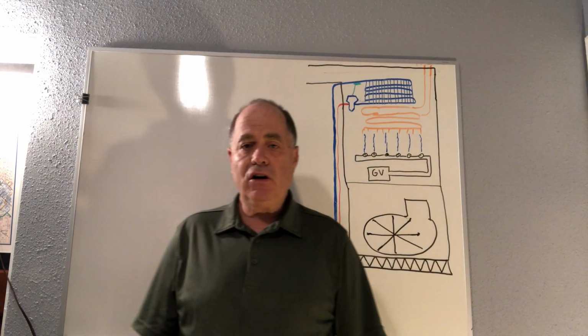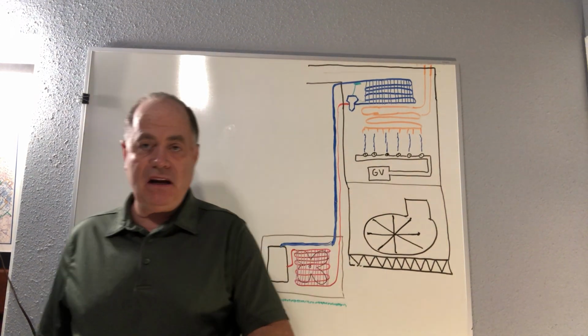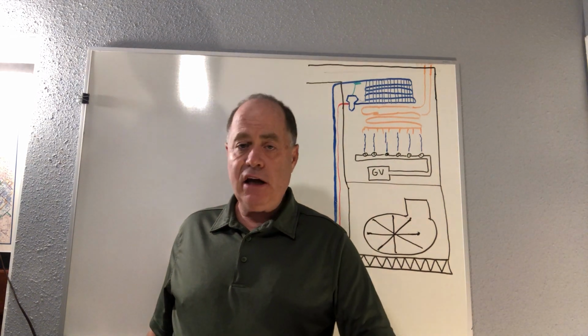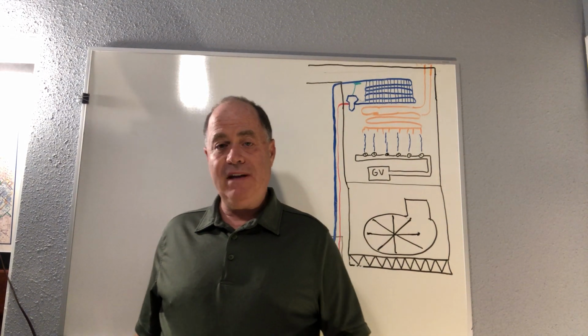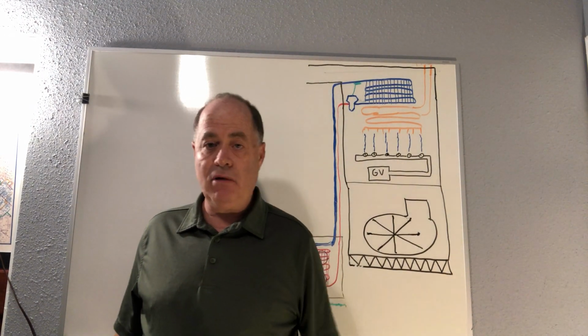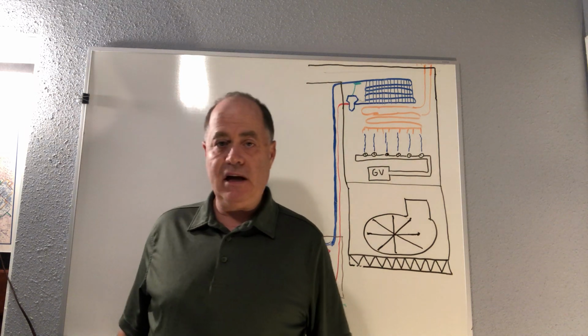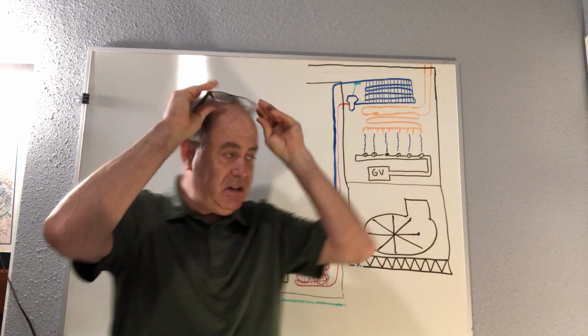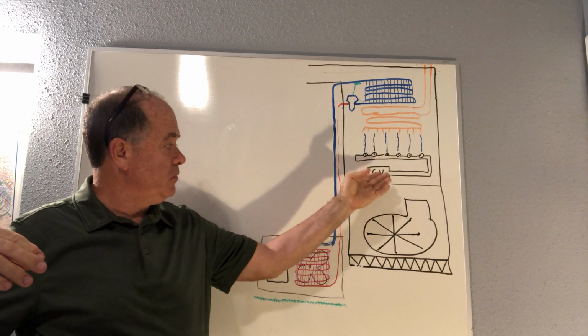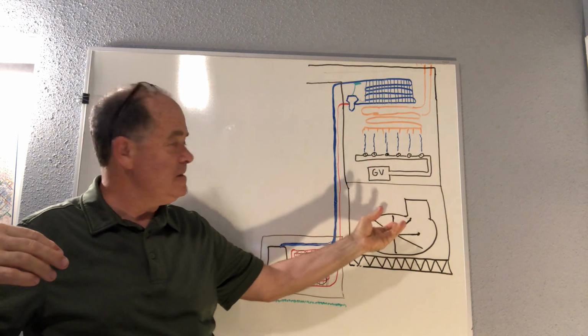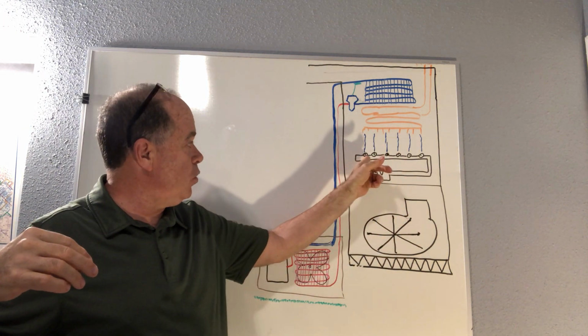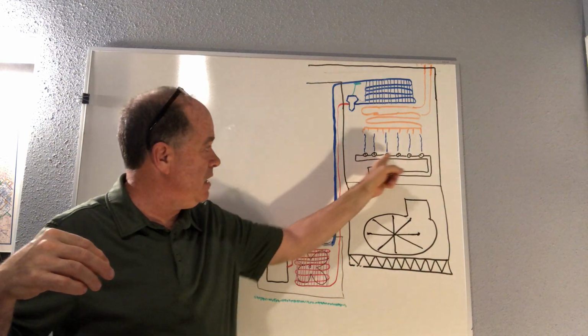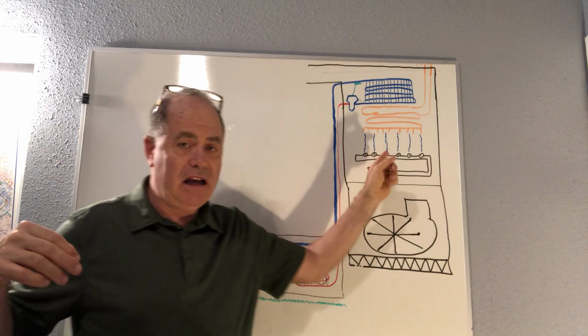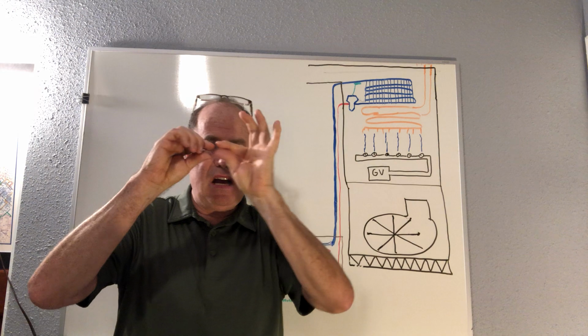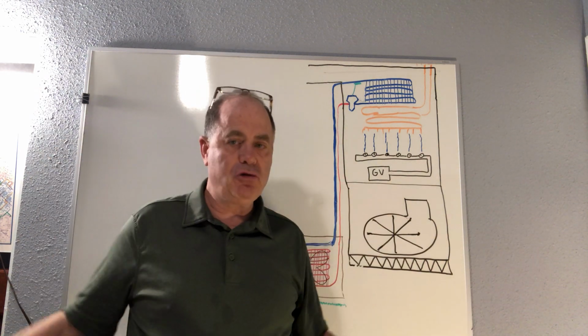Okay, here it starts off about the type of gases, and that if an appliance is designed for one type of gas, you can't just decide to modify it or use a different kind of gas. Like for instance here on this furnace, on this upflow type furnace, there's these orifices or spuds that come off the manifold on the gas valve, and these openings are sized for, let's say, natural gas.